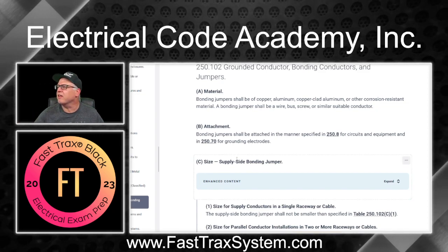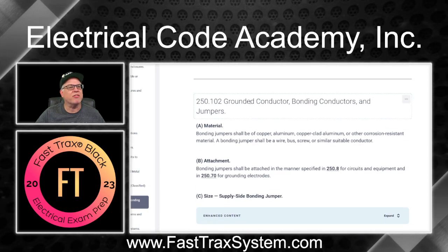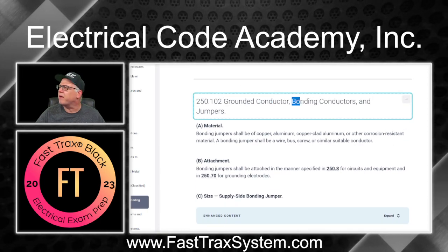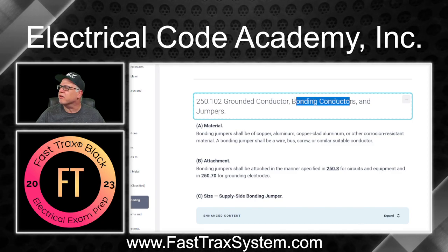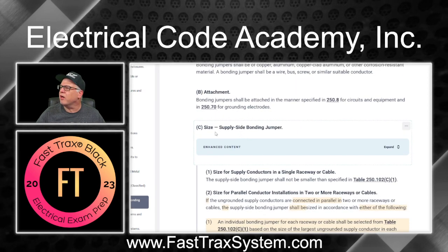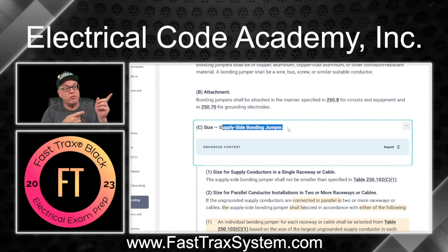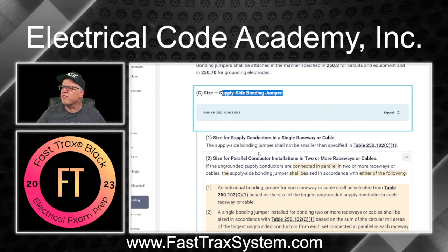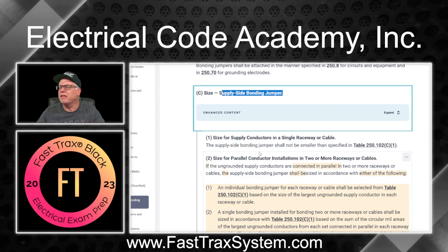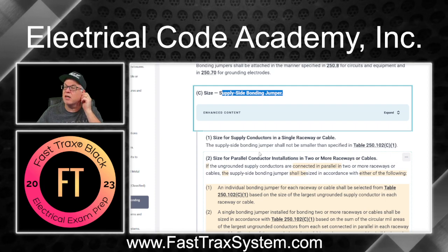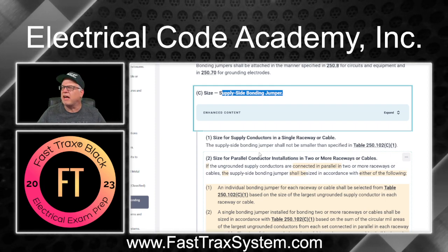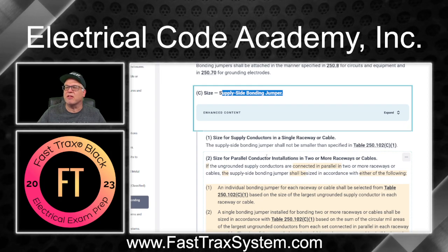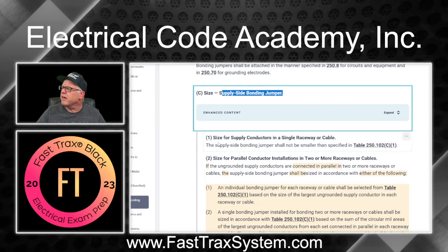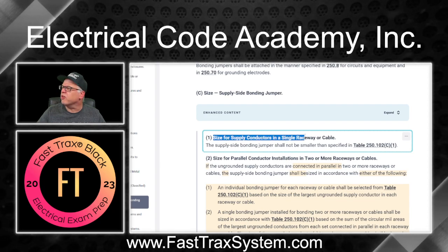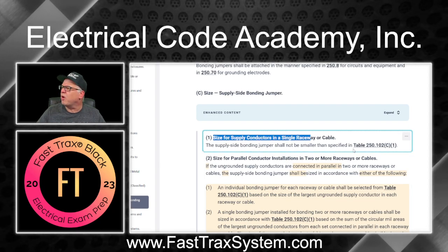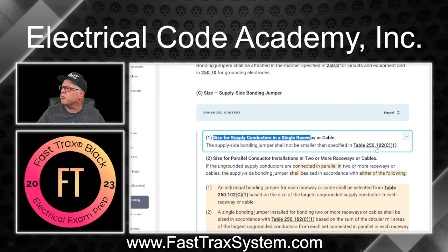All right, so let's look and see here. So here's 250.102. As you can see right here, it's for the grounded conductor, it's for bonding conductors and jumpers. So that's bonding conductors and bonding jumpers. So here we go: sizing, supply side bonding jumper. That's what our question was about. Now, if you notice down here, it says, and we only had one raceway, that's all it seemed to talk about, it says a service with a 500 kcmil conductor. Always assume copper unless stated otherwise. It's a 400 amp service, and it's talking about sizing a supply side bonding jumper. That was our question. Well, here we go. It's size supply side bonding jumper for a single raceway or cable. It just says shall not be smaller than in Table 250.102(C)(1), right there.